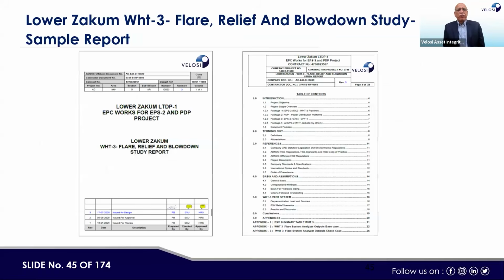So we normally do a relief system and blowdown study report. This study report covers what the fluids are, what the scenarios are where the system can be overpressurized, where the pressure would be relieved, and then what size of PSV should be there, what kind of PSV should be there from a type point of view, inlet size, outlet size, material of construction, and then what kind of relief header, what kind of knockout drum, then what kind of flare system. So all this, a complete study is carried out.